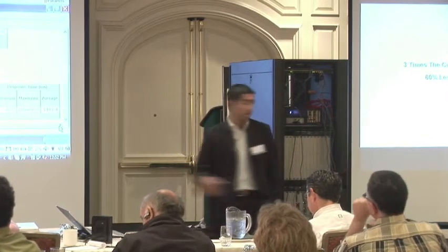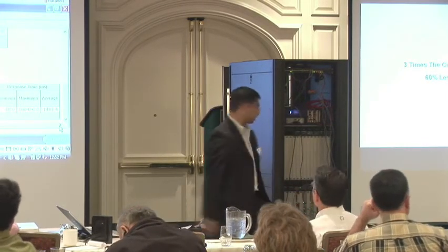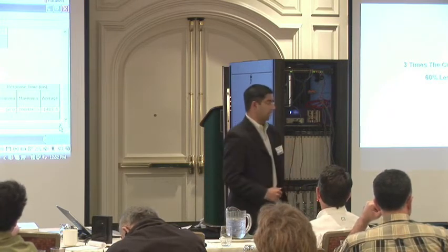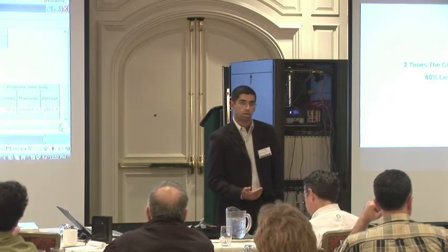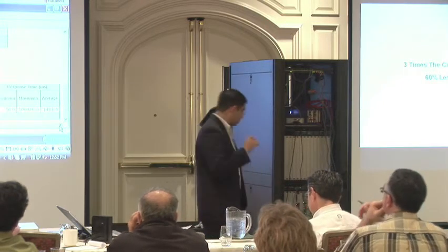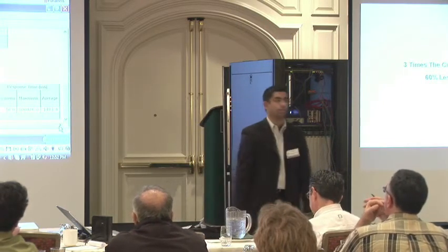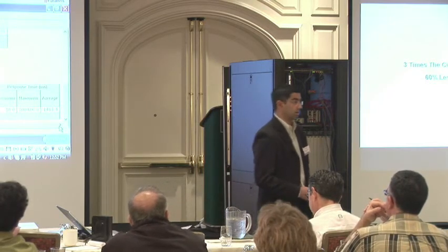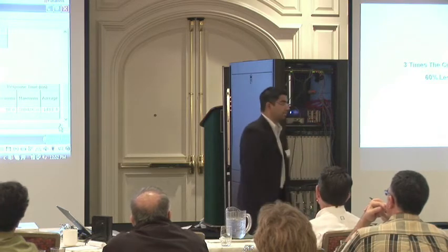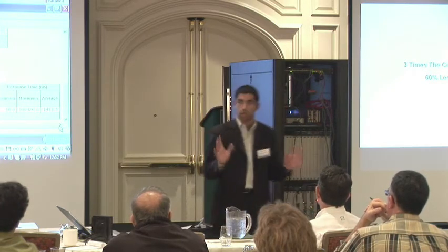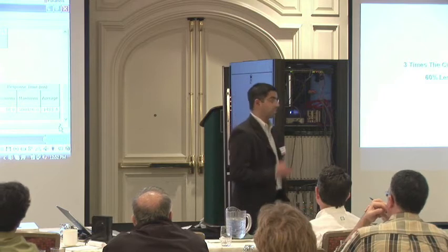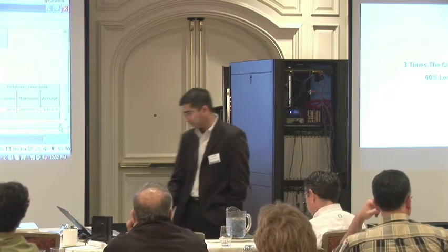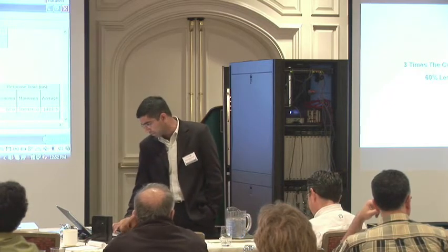If you saw me check that current meter there, another thing I noticed before I shut that equipment off was that the maximum amount of power used by the Dell equipment during that test — which you can now see is all off — was 15 amps of 120-volt power. So just these four pieces of equipment alone, when they were at peak load, used 15 amps of power. It's only 10,000 customers; I'll let Ken do the math for you on what the impact is if you have more customers.